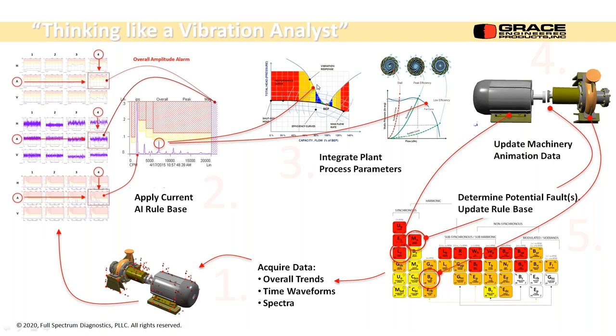Okay. We can also pull in plant process parameters, pump curves, fan curves that might be something that we can pick out that's useful in there, where we're operating on the curve when something like this happens and we get a high vibration. So it might just be an operational problem. The best efficiency point is right there where you'd have minimum vibration. You stray away from that on a pump and you'll either cavitate or recirculate and the vibration levels will go up. So if we can integrate those plant processes, it's fantastic. This one is something that Grace is working on. This is phase analysis. So we can look on the same transducer from X, Y, and Z's to see what the dominant response and the phase response is. But the real power in that is having the transducers talk to themselves. So I have four different transducers.